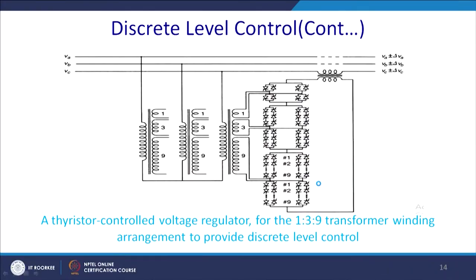So, this is the case here. The total circuit is shown for phase 3. So, you can inject different kinds of voltage in phase with delta V. So, that can be this, that can be this, or that can be this. So, this is the beauty of the discrete level transformer with 27 steps. The thyristor control voltage regulator with 1, 3 and 9 transformer winding arrangement provides 27 discrete level steps.